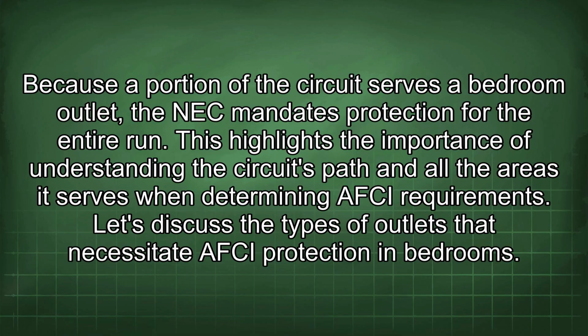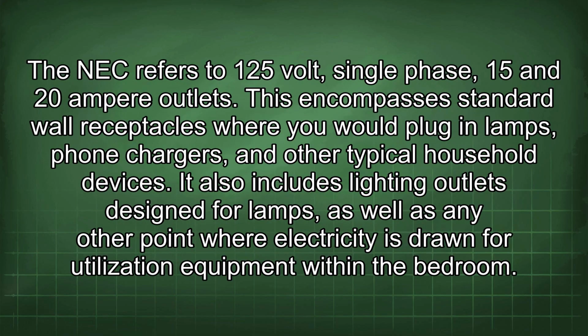Let's discuss the types of outlets that necessitate AFCI protection in bedrooms. The NEC refers to 125-volt, single-phase, 15 and 20 ampere outlets. This encompasses standard wall receptacles where you would plug in lamps, phone chargers, and other typical household devices. It also includes lighting outlets designed for lamps, as well as any other point where electricity is drawn for utilization equipment within the bedroom.